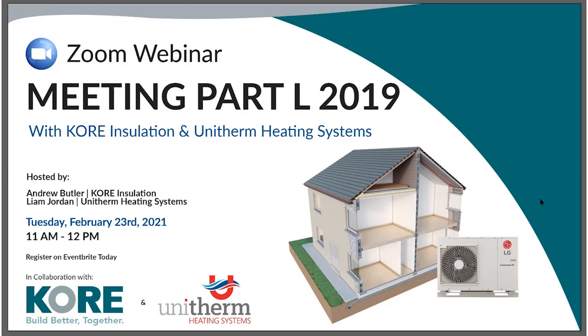And another one for yourself, Liam. What are the pros and cons of monoblock versus a split heat pump? So with the monoblock there, as I said, with the LG Therma V monoblock, I suppose efficiency is a big thing on this one. You have a wide operation range between 25 and 65, and when operating this at 30 to 35 degrees, you're basically running it at best efficiency point and highest COP.